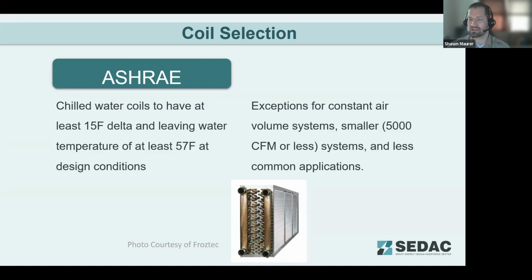Additionally, this can reduce the chance of low delta T, which can limit a chiller's output on the return side water flow. When you're designing with that 10-degree difference in your coil on a mild day, you're still sending pretty cold water back to the chiller. That has a serious impact on its overall efficiency. Pressure independent control valves can also improve control of comfort air and further increase the delta T of the coils. And so kind of ways to comply with this design standard.